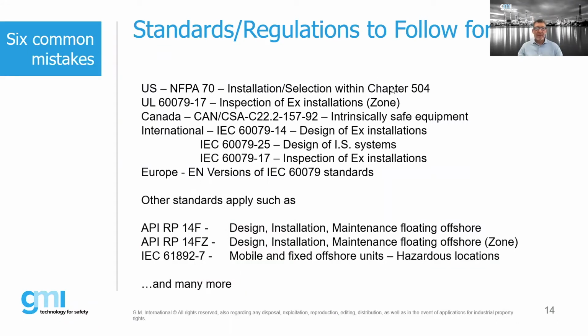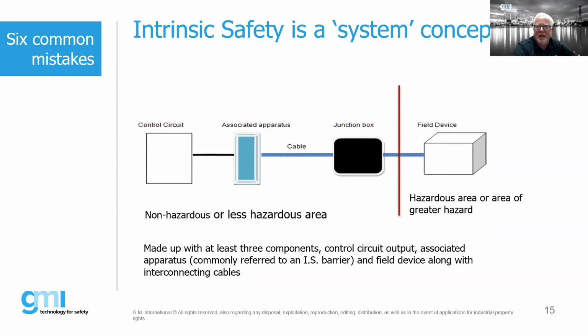So again, this is that slide again, just to reference, and I won't go through this again. One of the things about intrinsic safety that is important, as we teach under the IECEx COPC scheme, when we look at all the various protection concepts that are out there, such as Ex d, Ex e, or Ex p, they're typically standalone products. One thing that we always emphasize on intrinsic safety is that it is truly a system concept. As a system concept, we must take into account all of the various components that are part of that system.